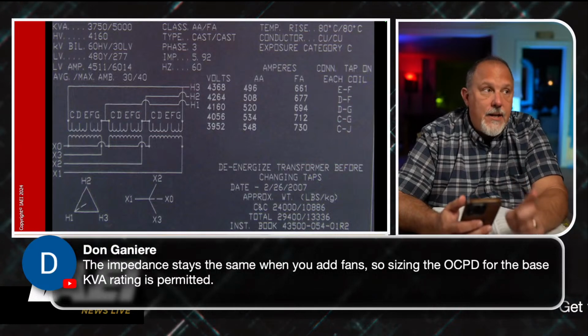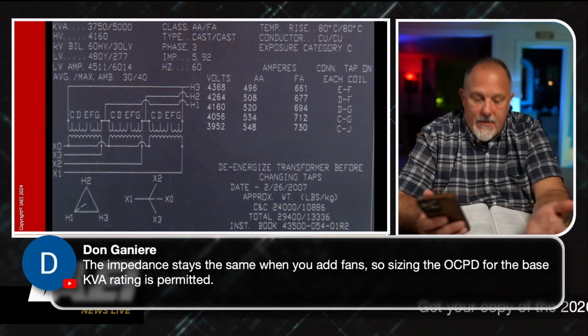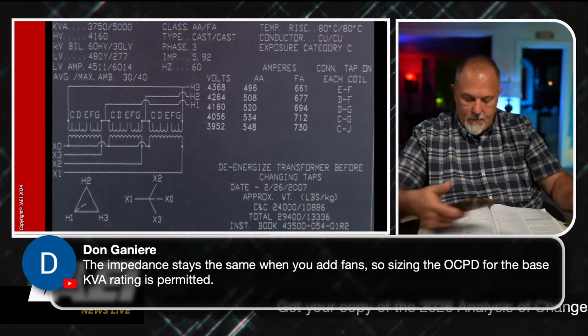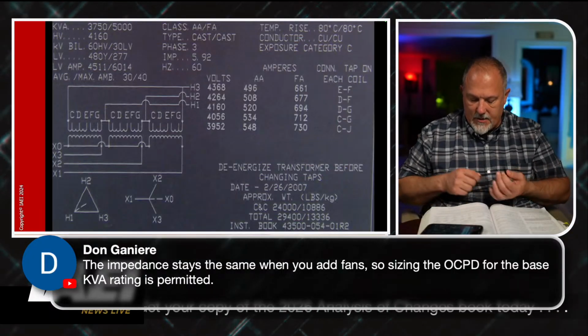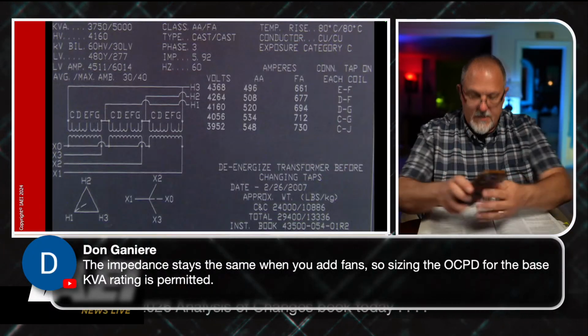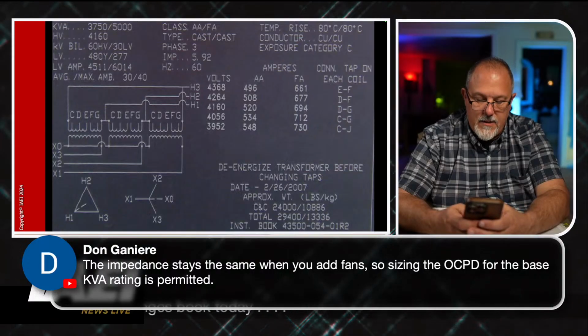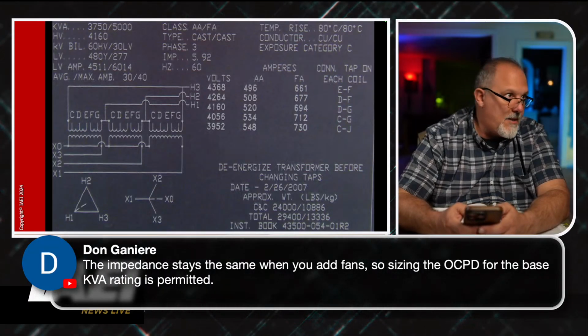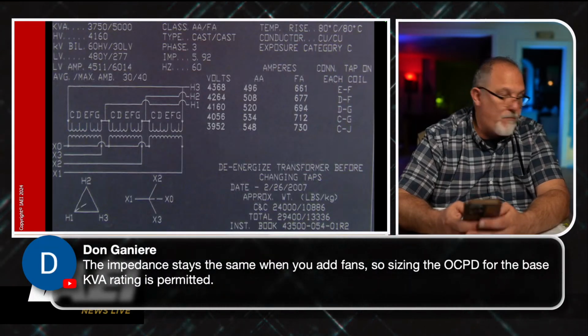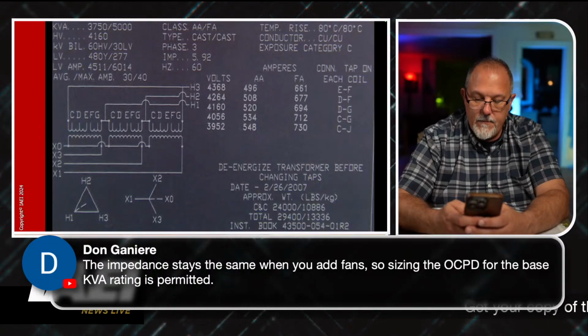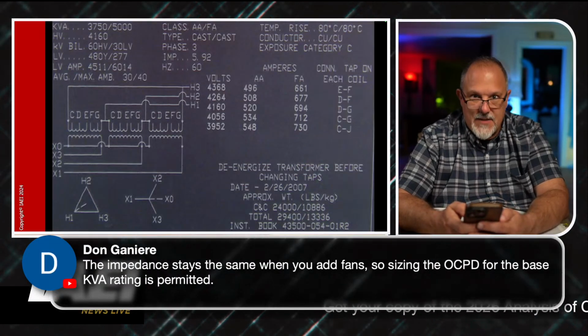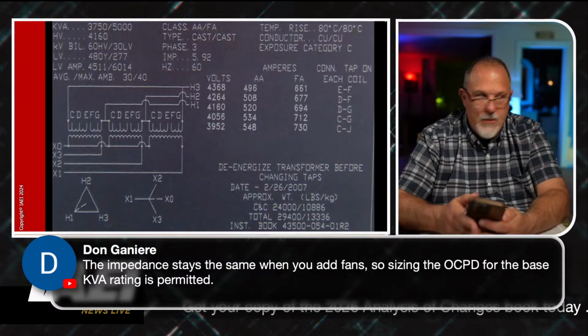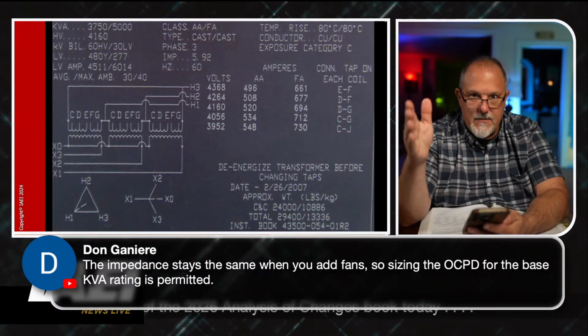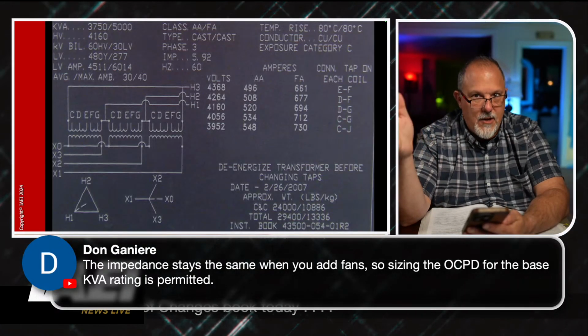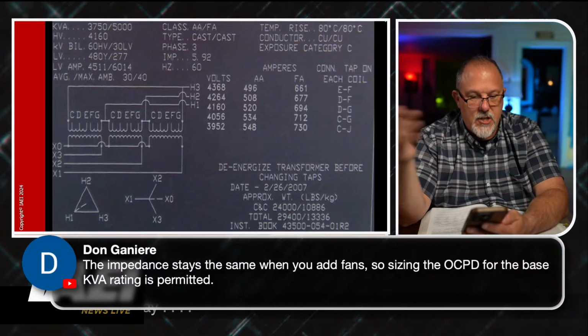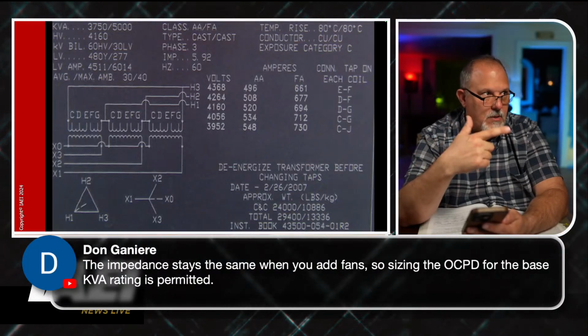I should at least make sure, but what am I permitted? I'm permitted up to 600% on a circuit breaker. So if I did 300%, if I did 3 times 520, I'm at 1,560. So my primary overcurrent protective device, which is only there to provide short circuit protection, is going to be much greater than the full load amps on the primary.